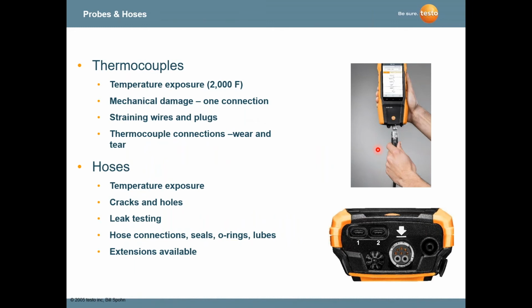We have thermocouples that go up to 2000 degrees Fahrenheit. Our typical sensors go to 1000 degrees Fahrenheit. What's unique with Testo is that we have one connection, so when you plug that probe hose in, you've got a flue gas hose here, a draft hose here, and a thermocouple connection here. With a hose like that, you're less likely to have cracks and issues with leakage on the hoses.